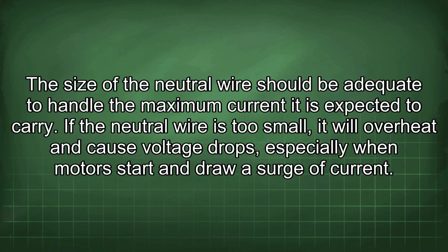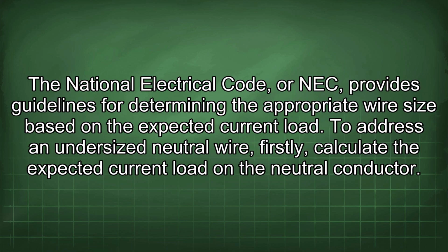The size of the neutral wire should be adequate to handle the maximum current it is expected to carry. If the neutral wire is too small, it will overheat and cause voltage drops, especially when motors start and draw a surge of current. The National Electrical Code, or NEC, provides guidelines for determining the appropriate wire size based on the expected current load. To address an undersized neutral wire, firstly calculate the expected current load on the neutral conductor.